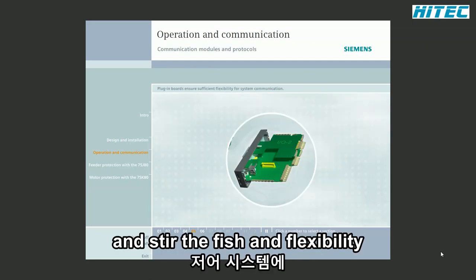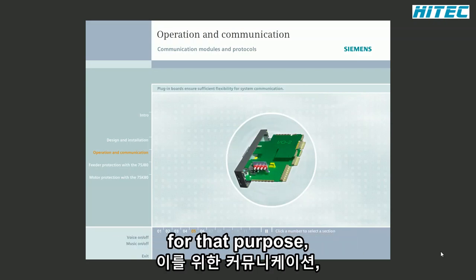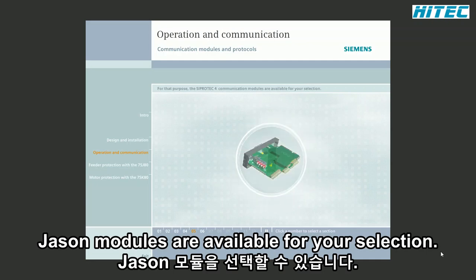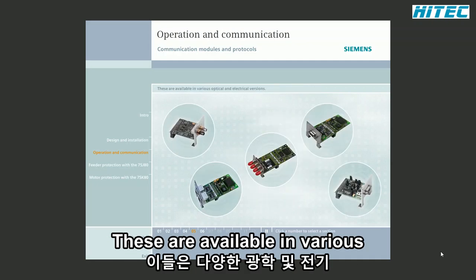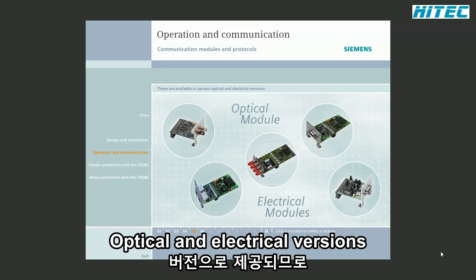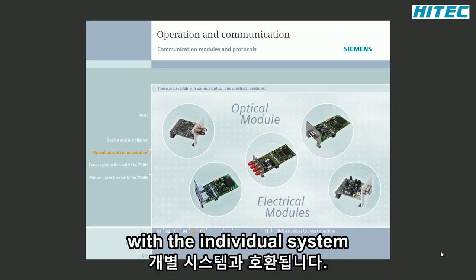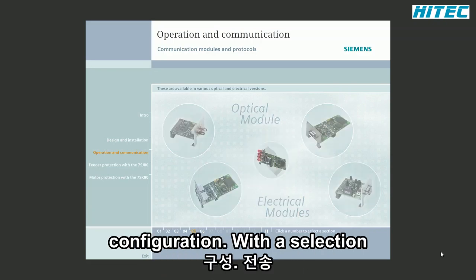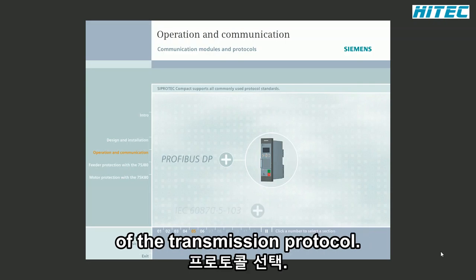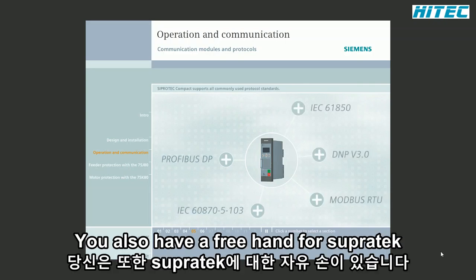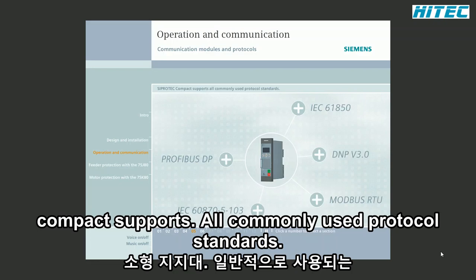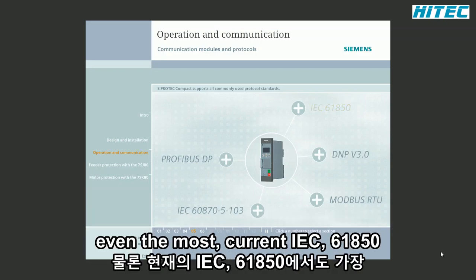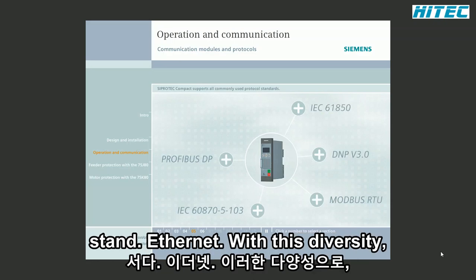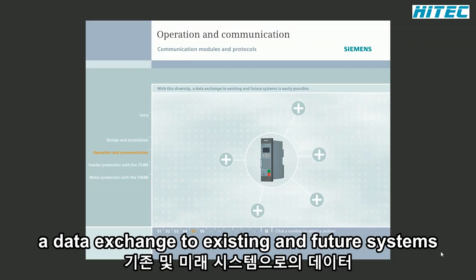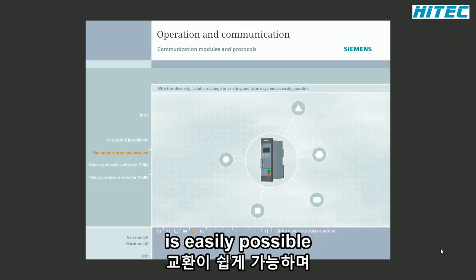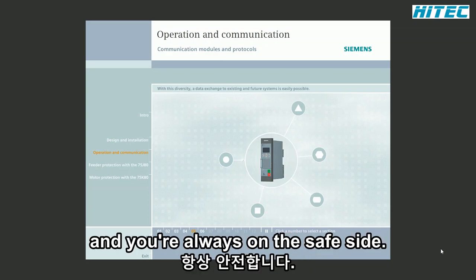Plug-in boards ensure sufficient flexibility for system communication. For that purpose, the SIPROTEC 4 communication modules are available for your selection. These are available in various optical and electrical versions and therefore almost always compatible with the individual system configuration. With the selection of the transmission protocol, you also have a free hand, for SIPROTEC Compact supports all commonly used protocol standards, of course even the most current IEC 61850 standard, in conjunction with Ethernet. With this diversity, a data exchange to existing and future systems is easily possible, and you're always on the safe side.